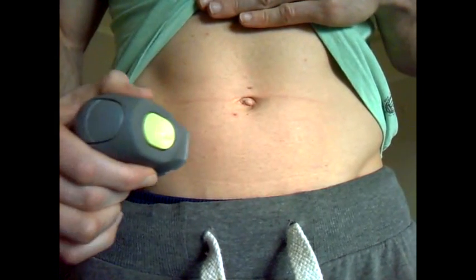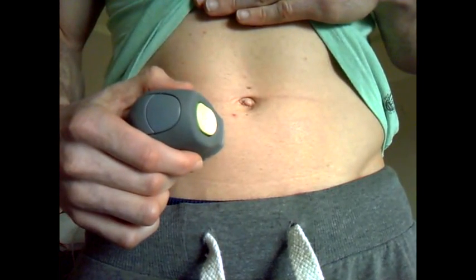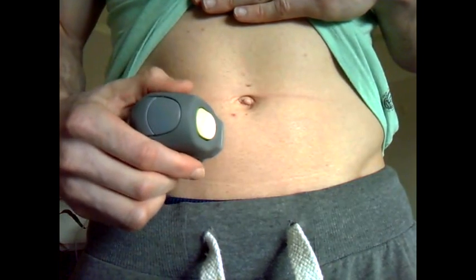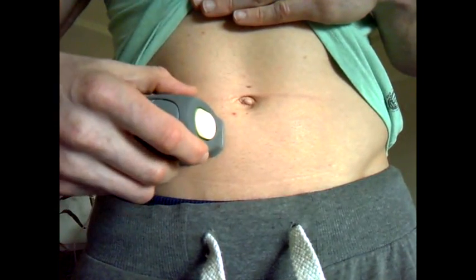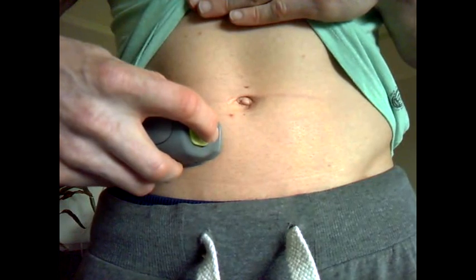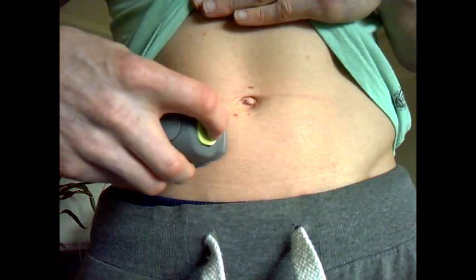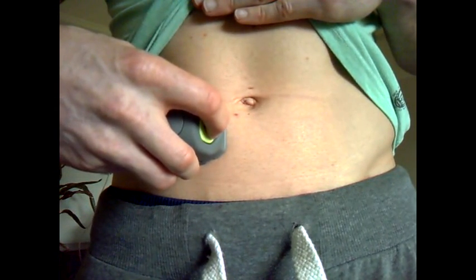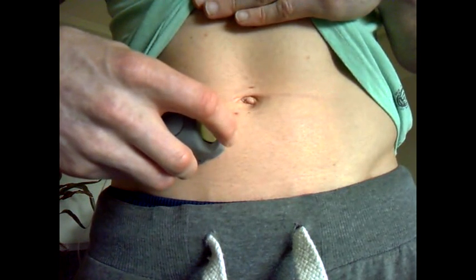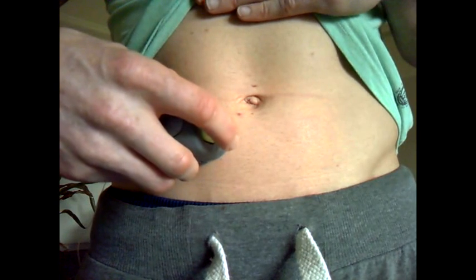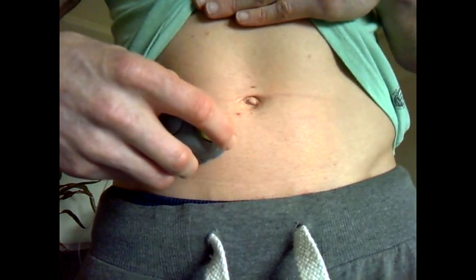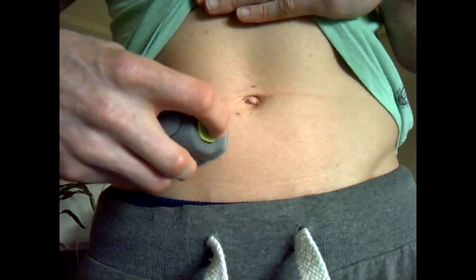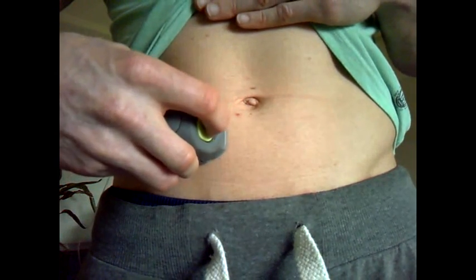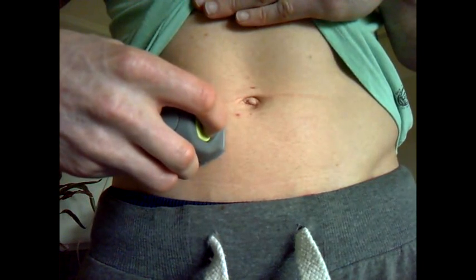You just pop the sensor onto the area that you want, and then this is the part now where you push the green button in, and then when you release it, that's when it inserts the sensor. Count to 5 seconds. 1, 2, 3, 4, 5. Now this point is really important, to push the green button in and keep it pressed in, and then lift off at 90 degrees.